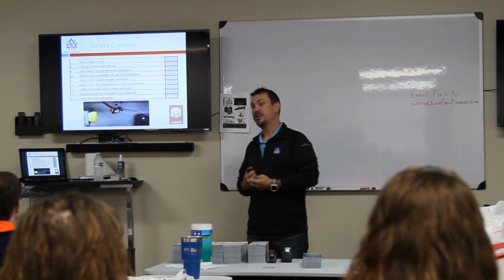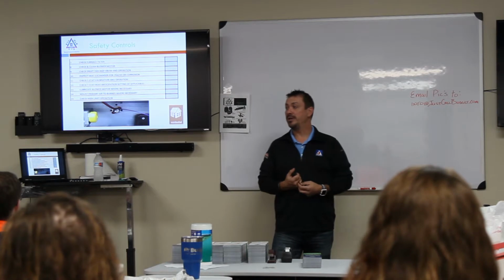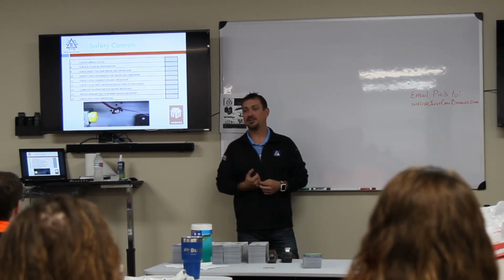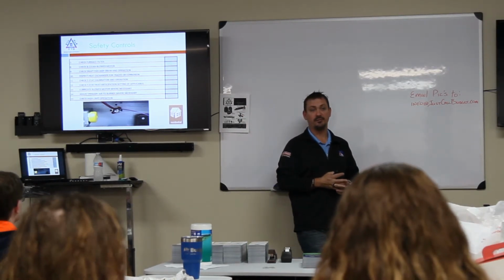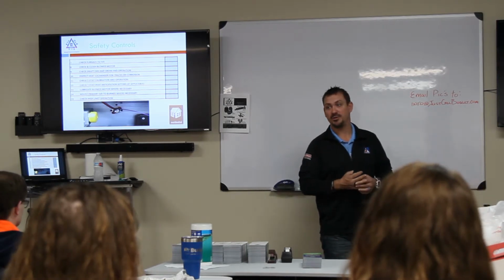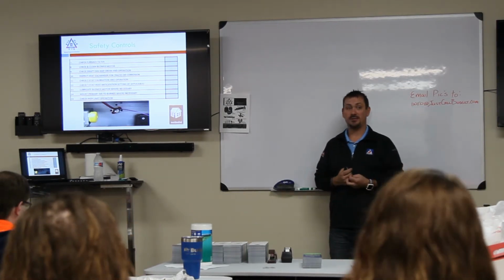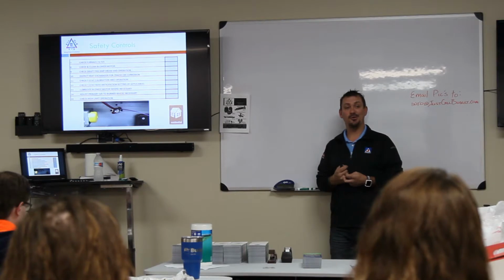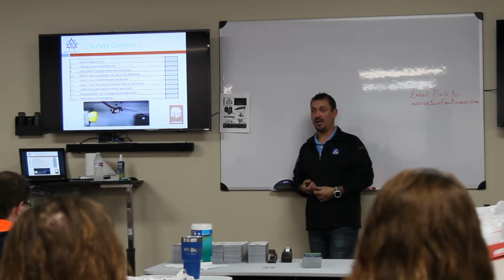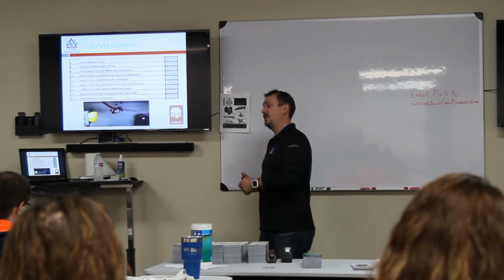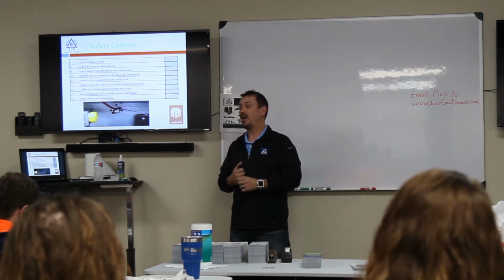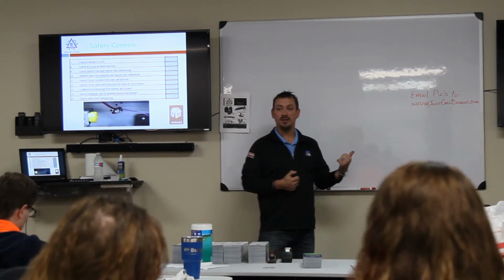92% of every pressure switch that we fail is actually good. 92% of them. How many of you guys have probably replaced pressure switches in here? Quite a few of you guys, right? So you're sitting there looking at me going, 92% of them? I replaced the pressure switch and it fixed the problem. Not necessarily. So what happens is when that pressure switch gets back to the factory, it works.